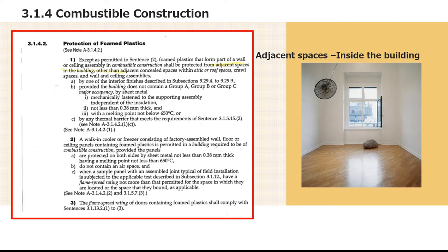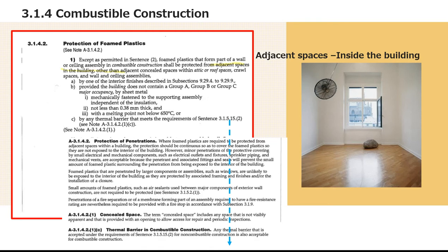We'll dive right into the combustible construction section. You'll find section 3142, protection of foam plastics. When you look at this section, you might immediately think it applies to all foam plastics, but that's not the case — this is for adjacent spaces within the building, not outside. Any thermal barrier must meet section 31515. The appendix confirms it applies to adjacent spaces within the building, which further cements that it applies inside the building.